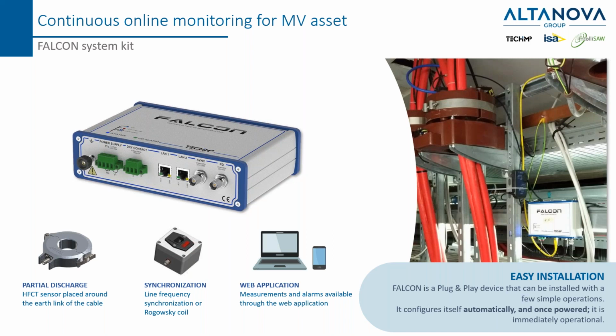The system is composed of the unit, sensors, and synchronization. I mean, we can also provide the synchronization tool, but it's typically available at site, using, for example, a Rogowski coil. And the software is totally inside the unit, so no additional software is needed. In fact, Falcon is a plug-and-play device that can be installed with a few simple operations. The unit configures itself automatically, and once powered, it is immediately operational.